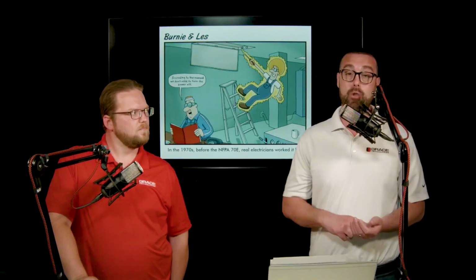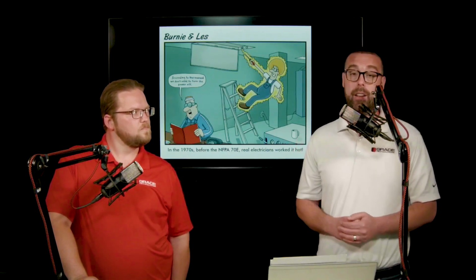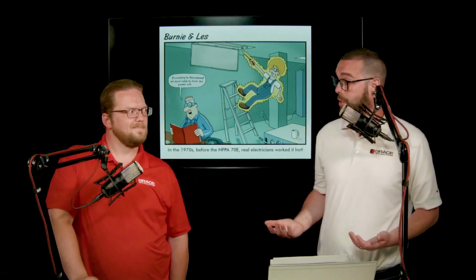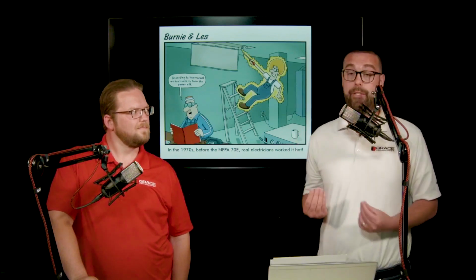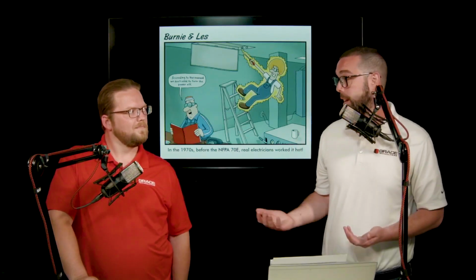The whole idea here is you can quickly walk up to our device, get a quick and easy visual indication for the presence of voltage. The device will come standard with dual redundant LEDs, 2 per each phase and 2 on the ground. So again, if there were any requirements for troubleshooting, or say you lose power on a particular phase, you have voltage running to the ground, or say you installed this on the load side of a disconnect. You flip your disconnect switch trying to isolate the power. However, the indicator is still illuminating on a particular phase. That would be indicative of a stuck blade scenario, right?